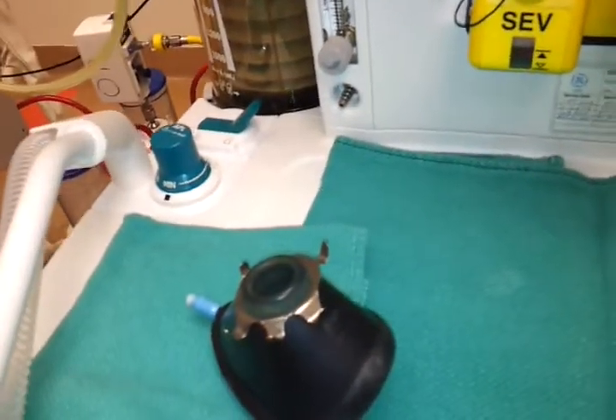There's the one more test, the calibrate flow transducers. There's a little piece on the side right here. Basically, this part right here. There's a little switch on the bottom that you can pop out, and you just gently wiggle it out. So you just leave it outside its position for a second. You should see an alarm come up here.